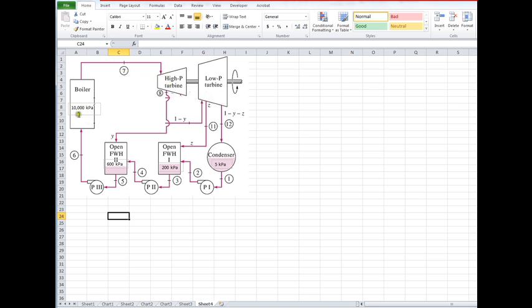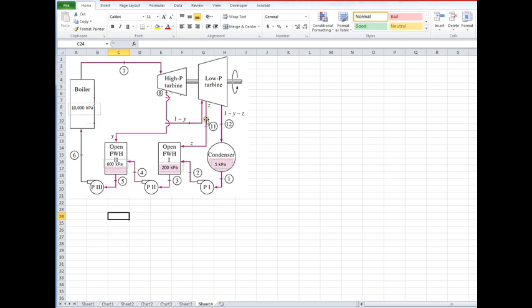We have 10,000 kPa expands to 600 kPa and some is extracted. Then the part that doesn't go to the feedwater heater continues into the low-pressure turbine, expands to 200 kPa, and the part that doesn't go through 200 kPa goes all the way through to the condenser at 5 kPa. So we really have three segments to this turbine.